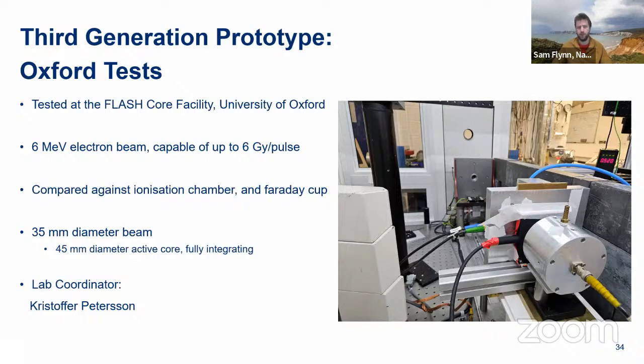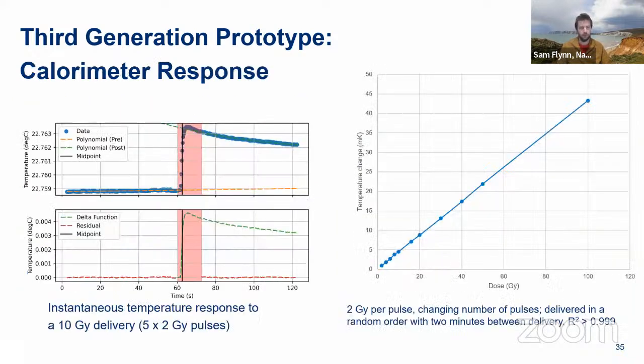The studies were compared against an ionization chamber, which is positioned in the beam halo, that will be sensitive to ion recombination, but being in the halo, it's experiencing a lower dose rate, so it's not as sensitive. Right. And here's some results from it.